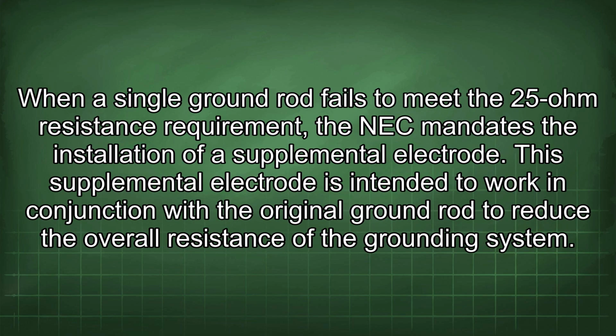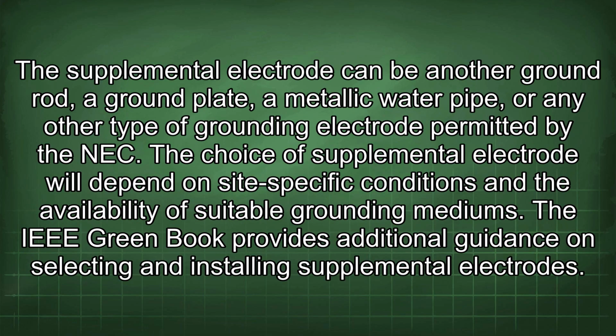When a single ground rod fails to meet the 25 ohm resistance requirement, the NEC mandates the installation of a supplemental electrode. This supplemental electrode is intended to work in conjunction with the original ground rod to reduce the overall resistance of the grounding system. The supplemental electrode can be another ground rod, a ground plate, a metallic water pipe, or any other type of grounding electrode permitted by the NEC. The choice of supplemental electrode will depend on site-specific conditions and the availability of suitable grounding mediums.